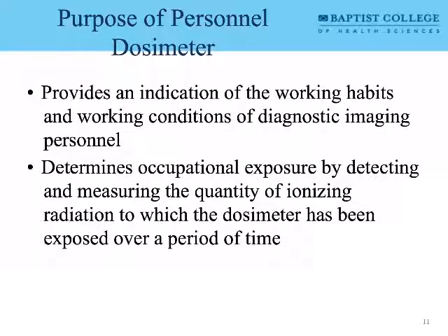So that thing measures different parts of your body? Is that what you're saying? Not necessarily. It only measures in this area, but anytime your body is exposed to radiation, any kind of flux, there's different filters inside of it which determine how deep the radiation was able to get. So the lower energy radiation, they're going to say that was an eye dose and only got to the lens of the eye. The higher energy exposures that we received is going to say it's a body dose because it got to deep tissue. Does that make sense?